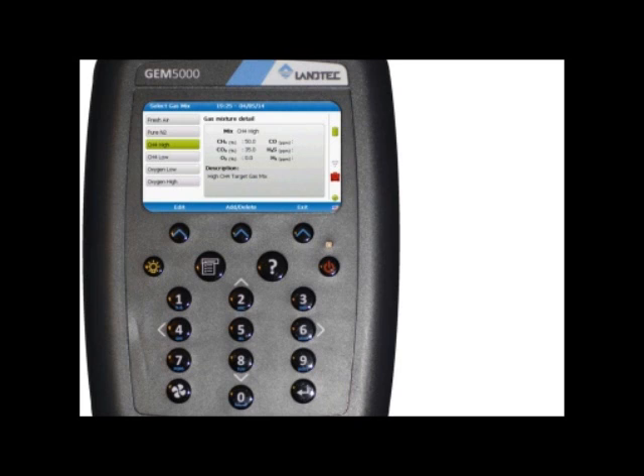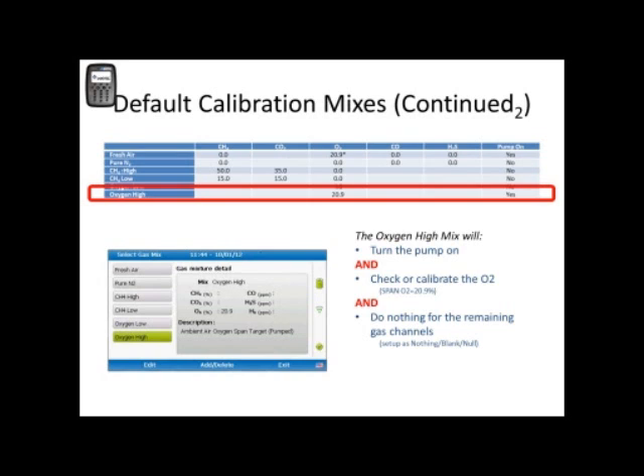Now moving forward to step number 3, which is our last step, we're going to keep pressing key number 8 again to scroll down to select our oxygen gas mix. In this example, we'll be using the oxygen high gas mix. Once selected, press the enter key. Once again, the default gas mixes are pre-configured from the factory. Focus is on this O2 high gas mix, and keeping in mind again the 3 basic commands that the GEM5000 recognizes. Under the oxygen high gas mix, we can clearly see that the mix will check or calibrate the oxygen to 20.9 and do nothing for the remaining gas channels.